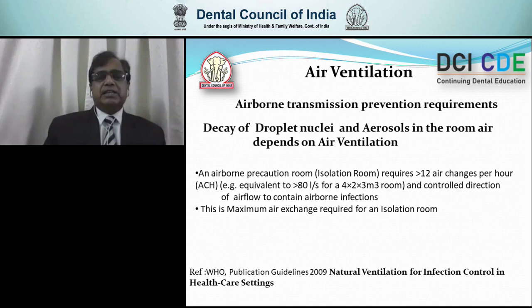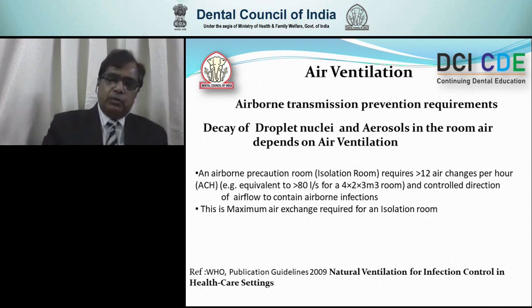This is the maximum air exchange required for an isolation room. For a dental clinic, where we mostly treat non-positive patients but perform many aerosol generating procedures, it's recommended that 6 to 12 air exchanges take place, preferably on the upper side, close to 12 air exchanges. This way, any aerosols containing COVID-19 will disintegrate within a few minutes, keeping your clinic free of infected aerosols.